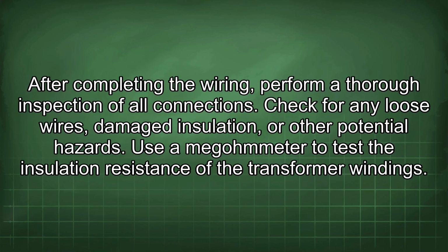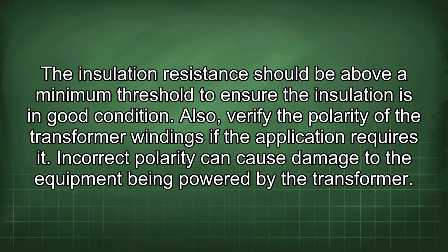After completing the wiring, perform a thorough inspection of all connections. Check for any loose wires, damaged insulation, or other potential hazards. Use a megohmmeter to test the insulation resistance of the transformer windings. The insulation resistance should be above a minimum threshold to ensure the insulation is in good condition.